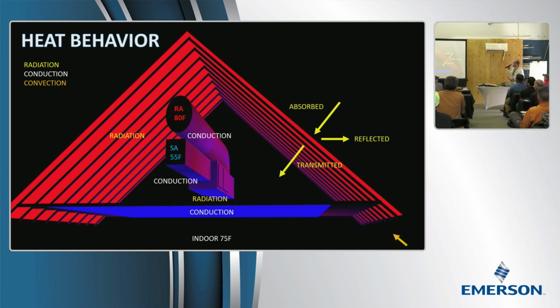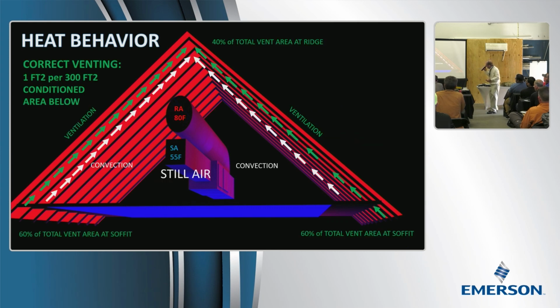Another thing to think about, right there we've got a return air duct on top of a cold cabinet. We're looking at normal venting here. The correct venting is 1 square foot per 300 square foot of floor area, and we want 60% of the area of that soffit to be at the bottom. We want 40% at the top. That path of moisture and outside air that's venting that roof, does it have any reason to come near the air handler? Not really. It's got a path set up, and it's limited, it's controlled. But that's not what we really build.